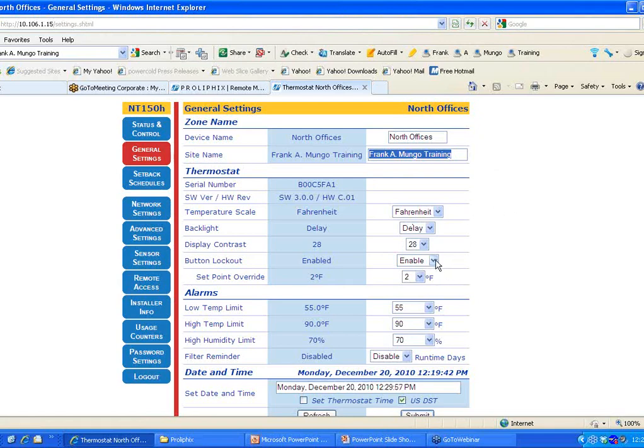I can lock it out. This one is locked out, but we do have it set up so that we can adjust the set point up or down a few degrees. You can see here I can set temperature limits and humidity limits. In this case, I have it set for a 55 degree low limit. If it's below 55 degrees, I will get a text message, as will the manager of that particular property and a few other people. I have a high temperature limit in here, and then I have a humidity limit.